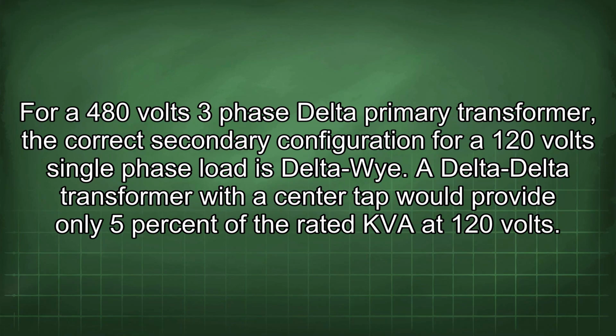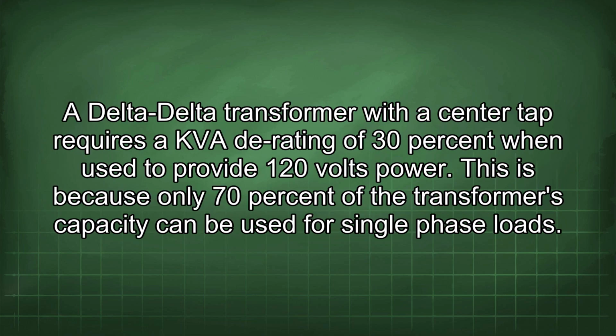For a 480 volts 3-phase delta primary transformer, the correct secondary configuration for a 120 volt single-phase load is Delta-Wye. A delta-delta transformer with a center tap would provide only 5% of the rated kVA at 120 volts. It requires a kVA derating of 30% when used to provide 120 volts power. This is because only 70% of the transformer's capacity can be used for single-phase loads.